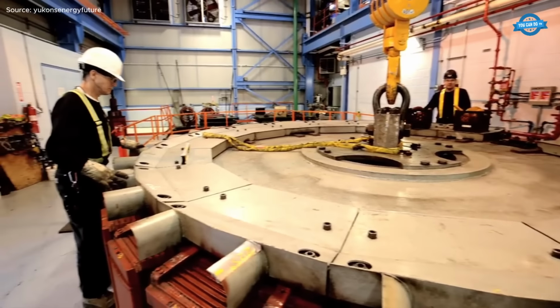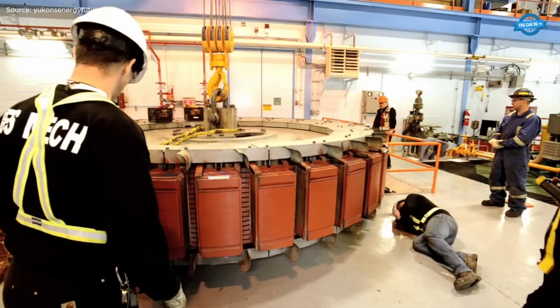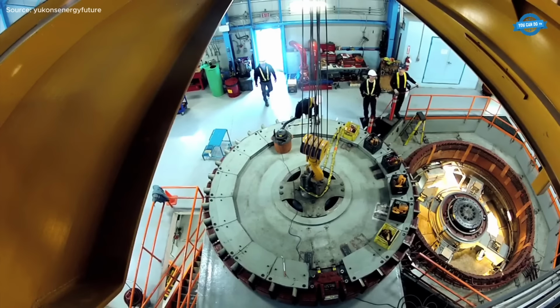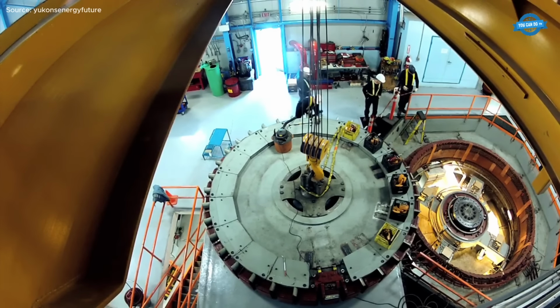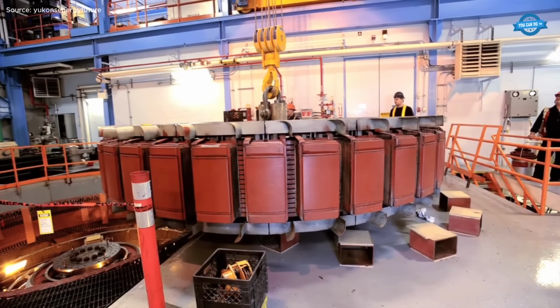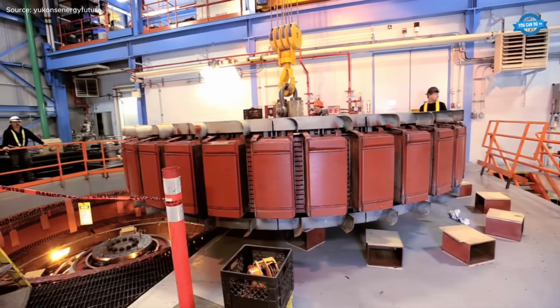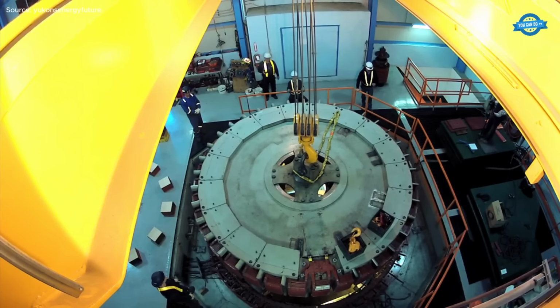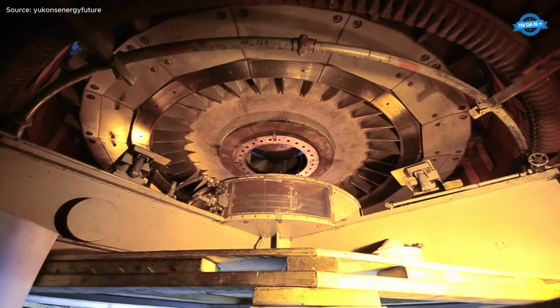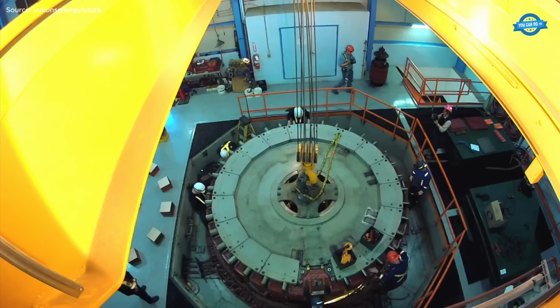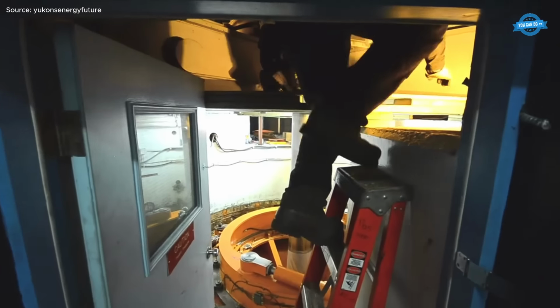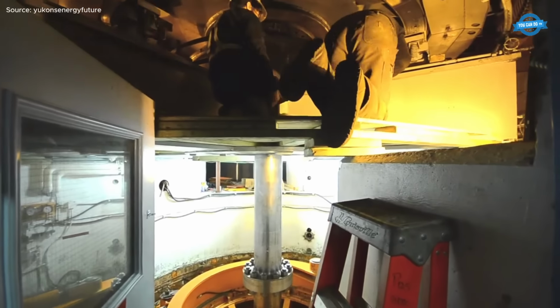Critical components such as guide bearings, thrust bearings, seals, and cooling systems are refurbished or replaced. The rotor is cleaned, rebalanced, and tested to ensure vibration levels remain within strict tolerances. After reassembly, alignment verification, electrical testing, and commissioning confirm the generator is ready to deliver another decade of dependable, renewable power.